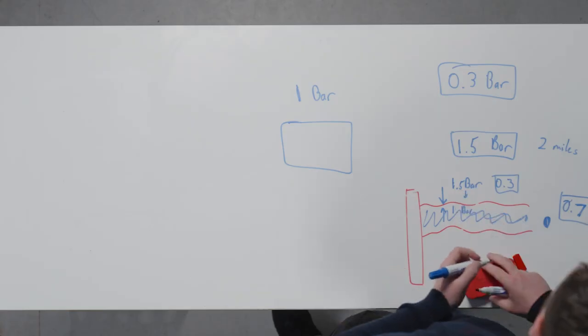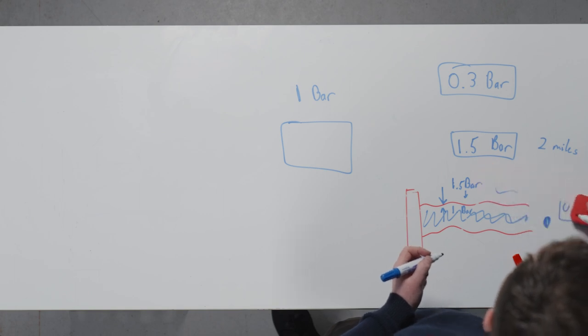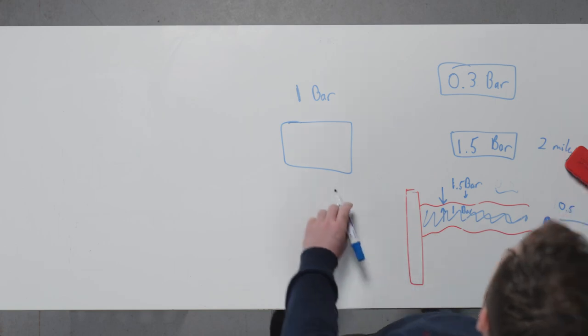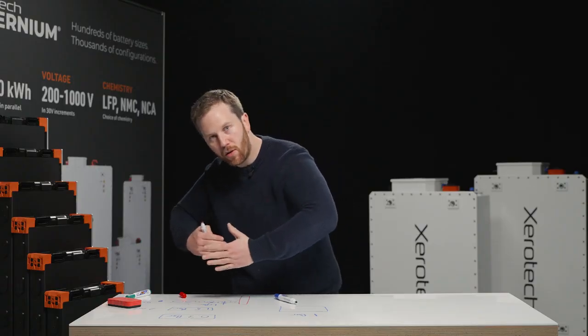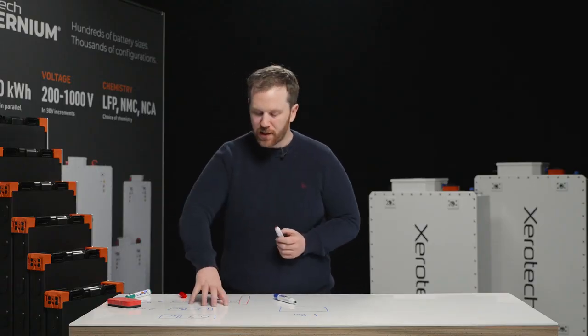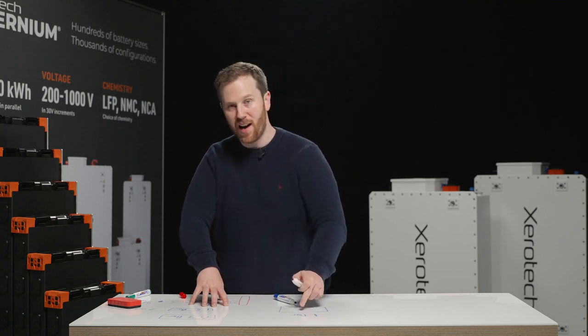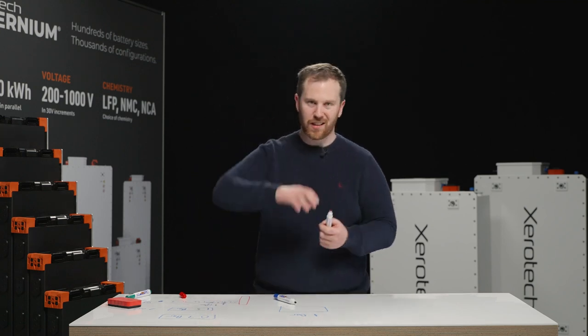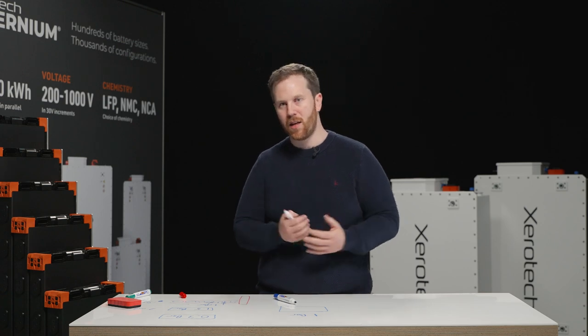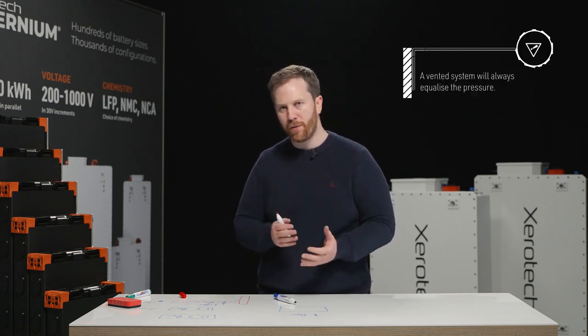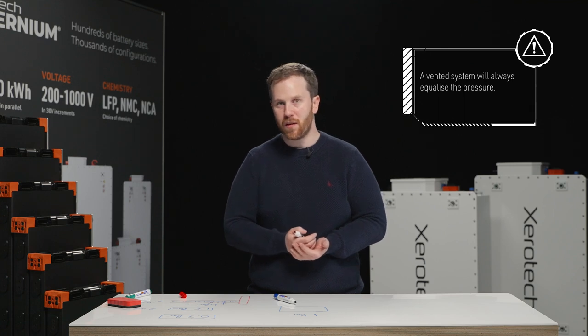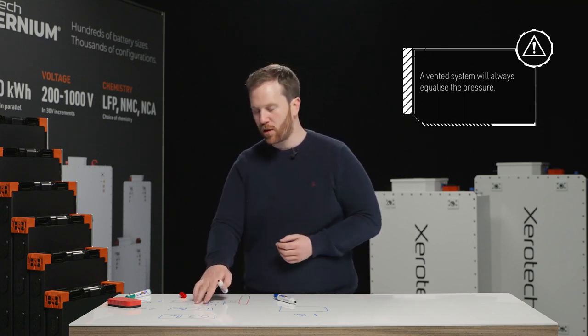The balloon is expanding. Similarly, if you go deep underground, the opposite happens. You could have 1.5 bar here, and you'll have a difference between the two. So you'll only be at half a bar. It's actually going to close the ducts in. It's going to try and force them a little bit shut. This happens if your system is not air vented. So if your header tank is a sealed header tank, not connected to the outside ambient air, you've got to be careful. So it's better if your system is vented because it'll always equalize pressure with the cooling system.